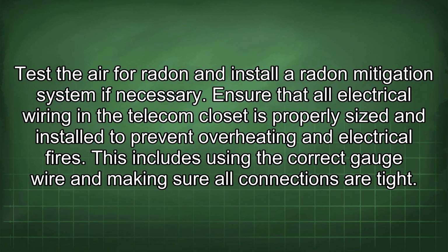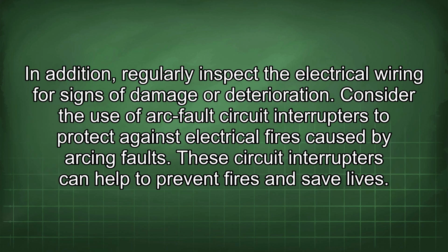Ensure that all electrical wiring in the telecom closet is properly sized and installed to prevent overheating and electrical fires. This includes using the correct gauge wire and making sure all connections are tight. In addition, regularly inspect the electrical wiring for signs of damage or deterioration. Consider the use of arc fault circuit interrupters to protect against electrical fires caused by arcing faults. These circuit interrupters can help to prevent fires and save lives.